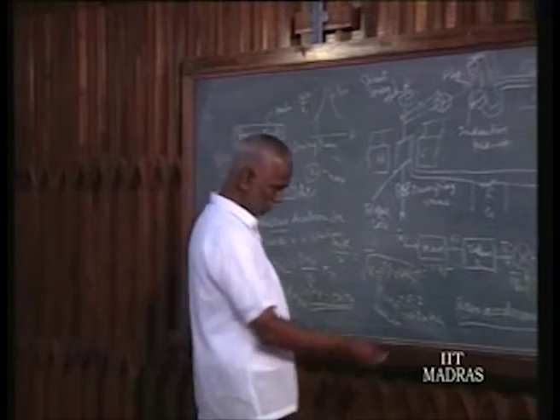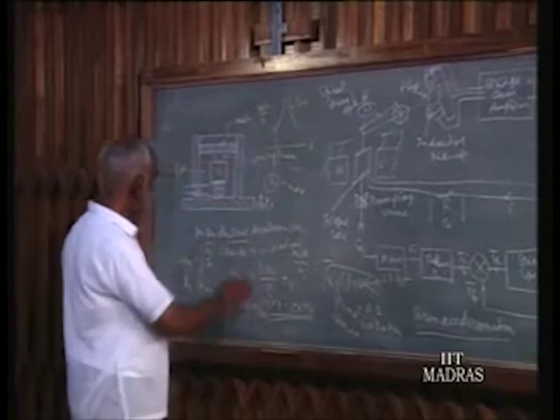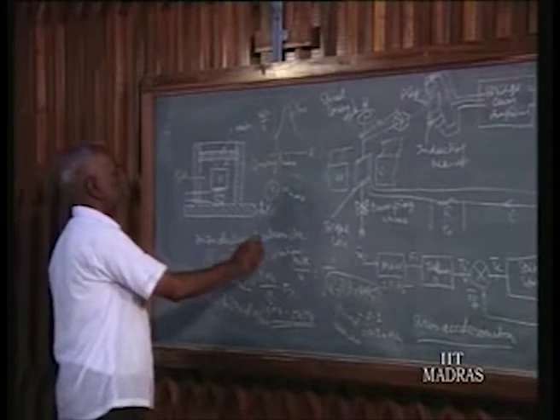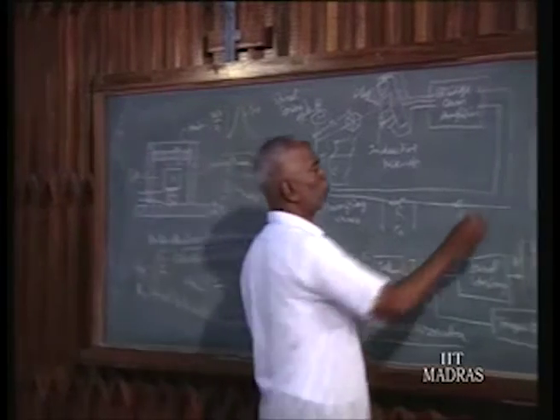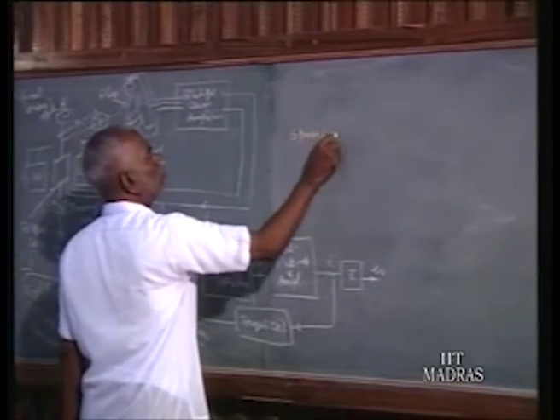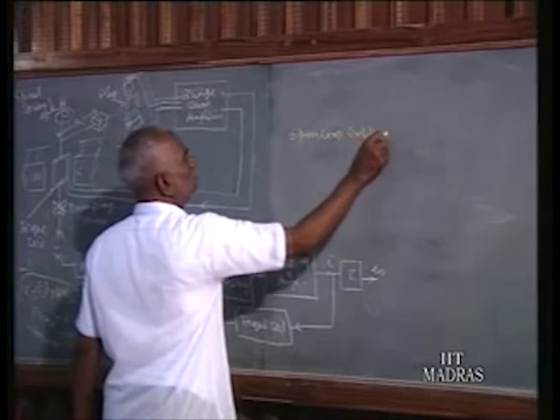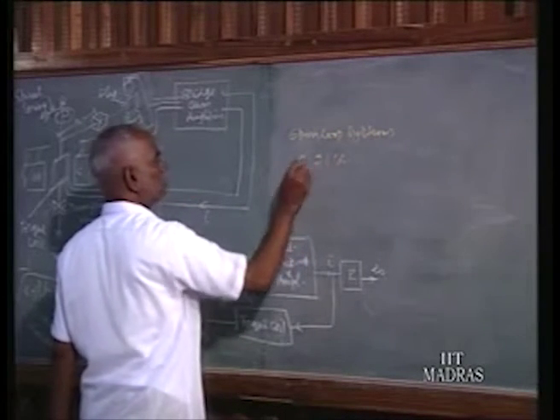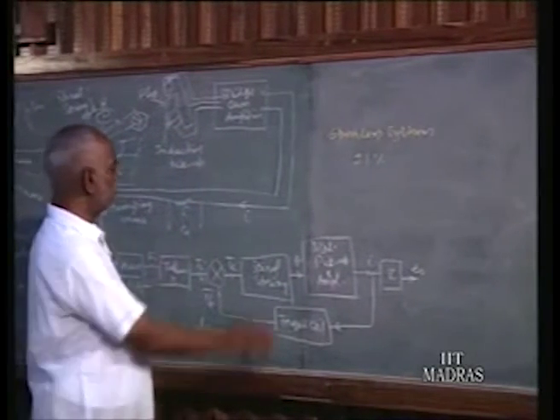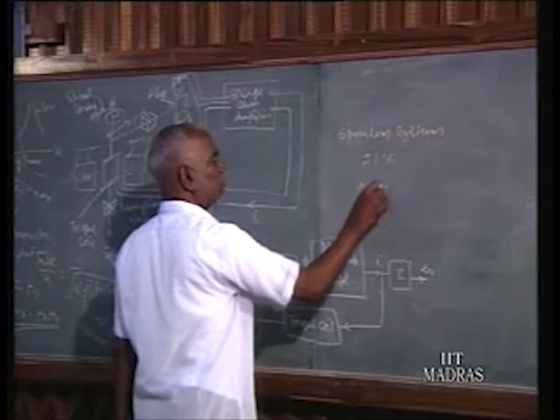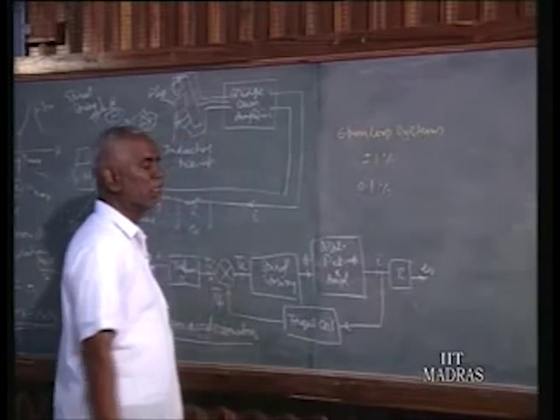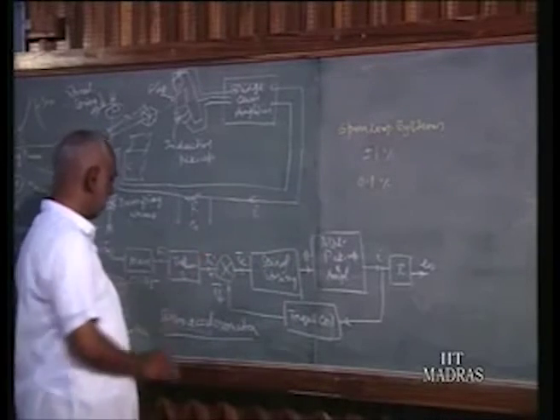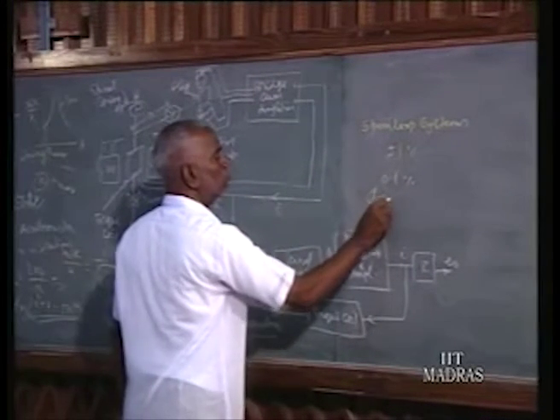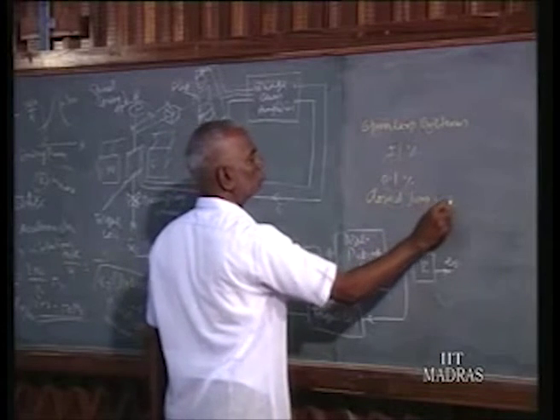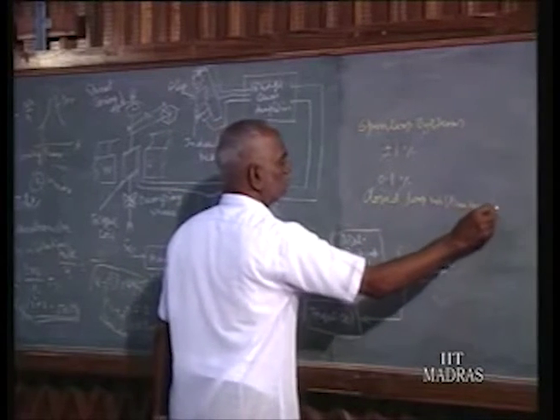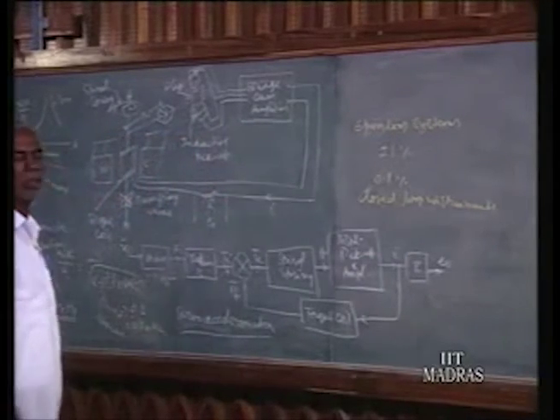Next type is servo accelerometer. So all these instruments up to here are open loop systems, open loop instruments. Their accuracy is, say, plus or minus 1% of the full scale. Whereas if you want to have 0.1% accuracy, or uncertainty, then you should necessarily go for closed loop instruments, and this servo accelerometer is one such closed loop accelerometer.